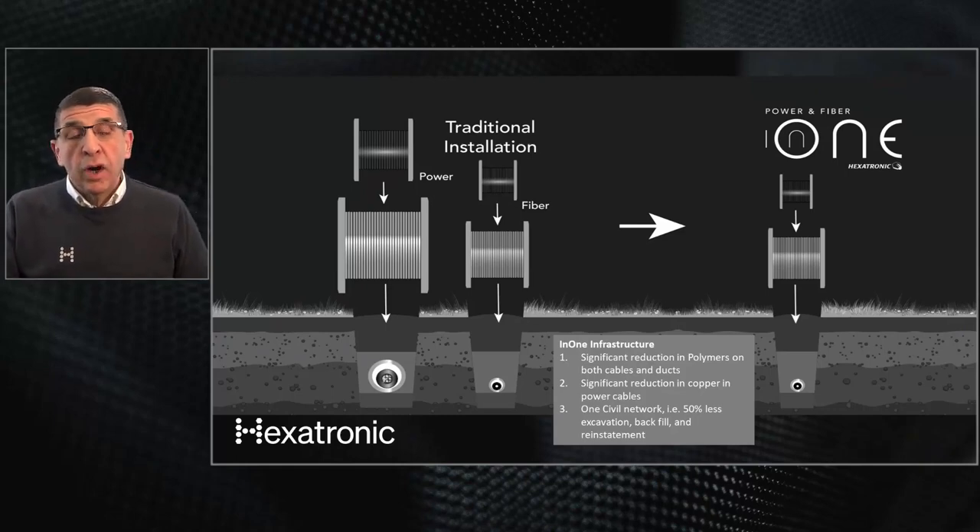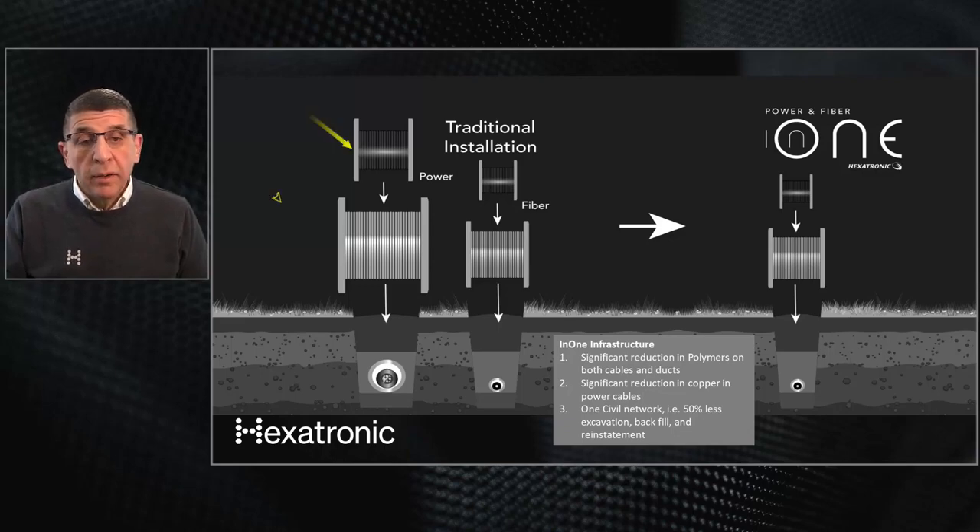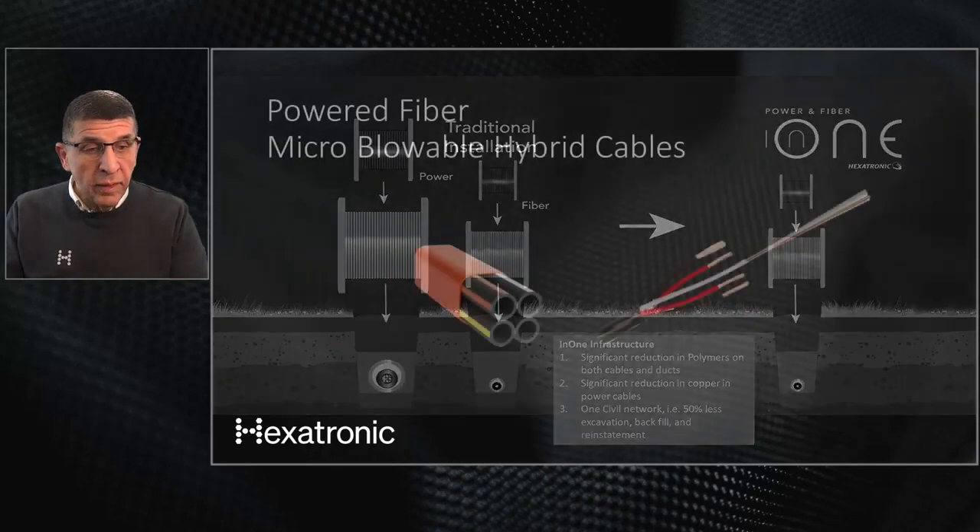Another dimension is the cross-section of the installation. In a traditional installation you need a power cable with its own duct and civil infrastructure, plus a separate fiber optic cable with its own duct and civil infrastructure — because most countries do not allow mixing power cables and fiber optic cables in the same civil infrastructure. With the InOne solution you have only one hybrid cable, one micro duct, and one micro trench for both power and fiber, making deployment much faster and less expensive.